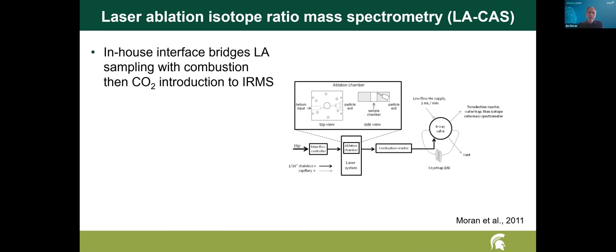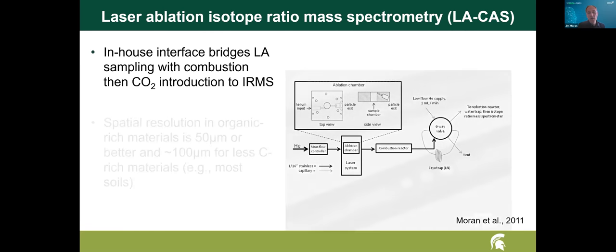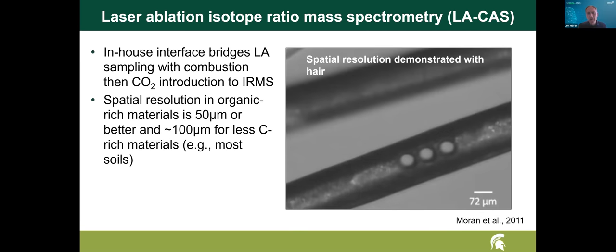We didn't make a laser ablation system, and we didn't make an IRMS system. What we made is the interface to connect the two. You put your sample in the laser ablation system, make CO2, pass that to the IRMS. We're taking the best of both worlds and merging them so we can get spatially resolved sampling with the quantification ability of that IRMS. Here's another example — this is a horse hair — and you can see these nice 50-micron diameter spots. For things like hair or nice polymers with a lot of organic carbon, we can get 50-micron or even better spatial resolution. If we start moving towards soil samples, there's a lot less carbon, so it takes more sample to get enough material to make the IRMS measurement, and we end up making about a 100-micron spot size in that sample.